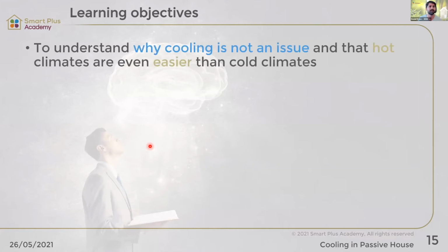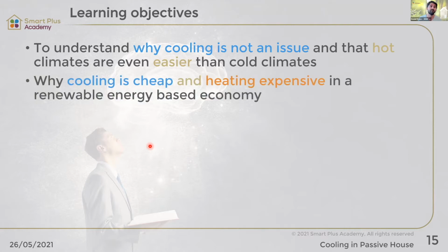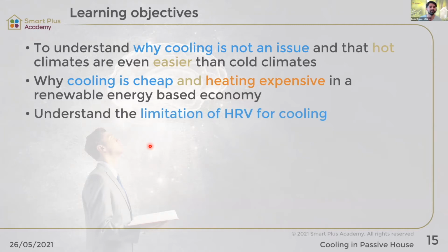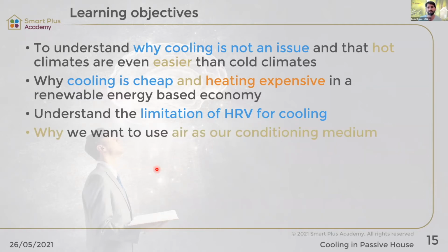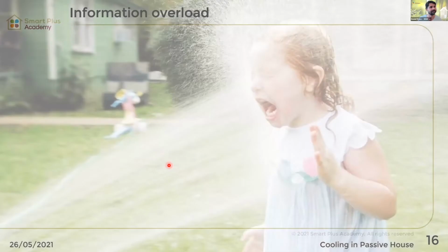So what's the learning objective? First, I want you to understand why cooling is not an issue, and that hot climate is far easier than cold climate. I want to explain why cooling is cheap and heating is expensive. Then I want to give you an understanding of the limitations of heat recovery ventilation systems for cooling, and why we want to use air as our conditioning medium rather than water or something else with a far higher energy density. So you probably realize I'm going through my slides pretty quickly, and you will get a bit of information overload.